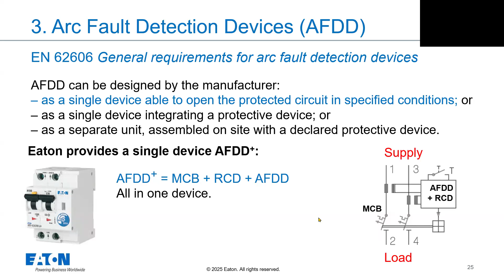In our case, when we speak about the Eaton version, the compact version, we also use the abbreviation AFDD plus, to express that everything that is important for protection is inside. It means MCB, RCD, and also AFDD. Then we can also distinguish between various producers, but in the end, the result is the same. And now, a very short explanation of what we need to discuss when we speak about types of faults, and to know which protective measure or which protective device will work and which will not work.